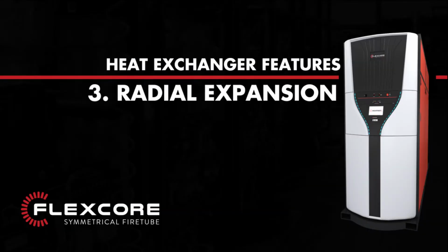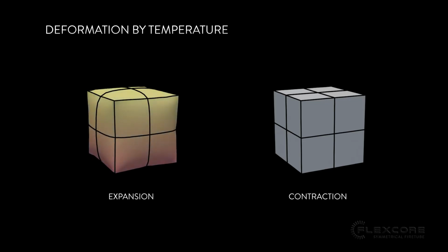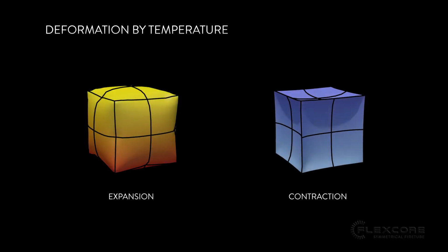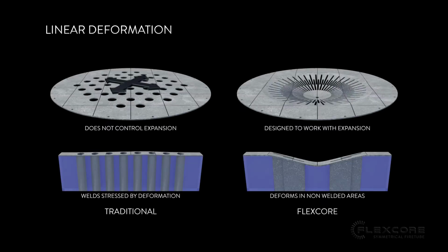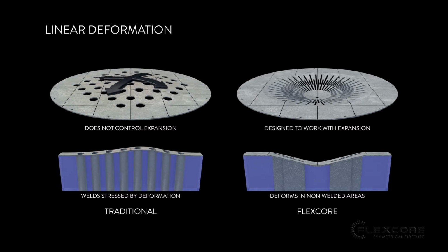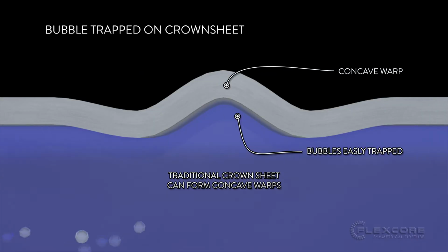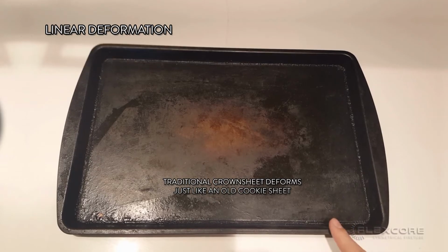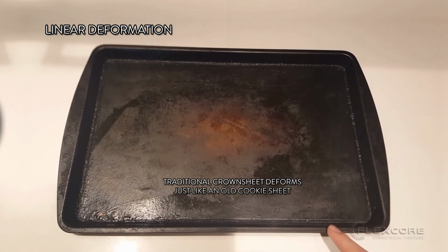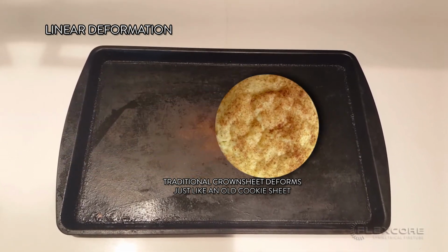3. Radial expansion. Matter expands when it heats up and contracts when it cools down. This is especially noticeable in the high heat conditions of a boiler's combustion chamber. A traditional crown sheet is flat and has a linear expansion, which can create inconsistent deformation. Inconsistent deformation can form concave warps in the crown sheet for air bubbles to get trapped in. Think of your mother's cookie sheet that doesn't sit flat after baking the first batch of snickerdoodles.